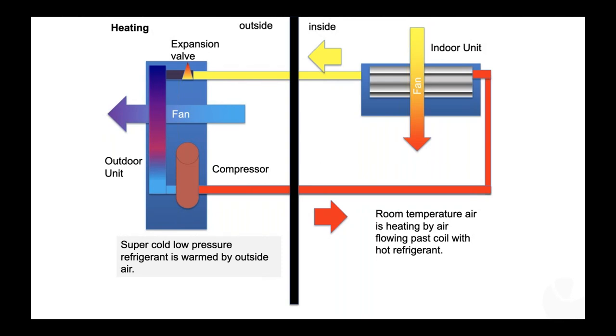They have very much, even the substitutes that may be coming down the road will have very similar physical properties. And the most important physical property that we're going to talk about right here is, as I mentioned, quickly going from how heat pumps work 101 to maybe 352, that the refrigerant has a boiling point of negative 50 degrees Fahrenheit. So when it goes through that expansion valve and it goes into a lower pressure state, around 100 psi in the outdoor coil, it dives for its boiling point.